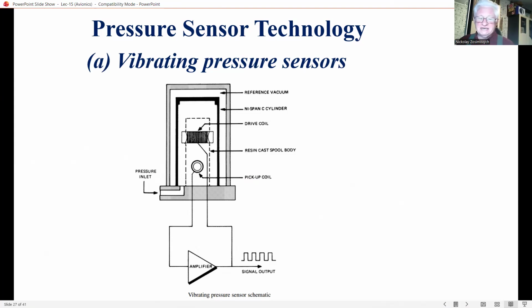The vibrating cylinder sensor is shown schematically in this slide. The pressure sensing element consists of a thin walled cylinder with the input pressure acting on the inside of the cylinder and with the outside at a vacuum reference pressure. The cylinder is maintained in a hoop mode of vibration by making it part of a feedback oscillator, by sensing the cylinder wall displacement, processing and amplifying the signal and feeding it back to a suitable force producing device. Electromagnetic drive and pickup coils are used so that there is no contact with the vibrating cylinder.